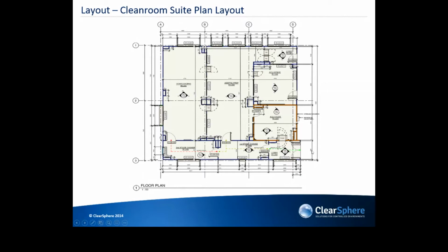Coming from outside, you're into the first stage lobby. You have the fire rated pass-through hatches we looked at in the photograph earlier. You're into the first stage gowning, then from there into the aseptic prep room and into the storeroom, which is outlined. That's the fire compartment we spoke about earlier as well.